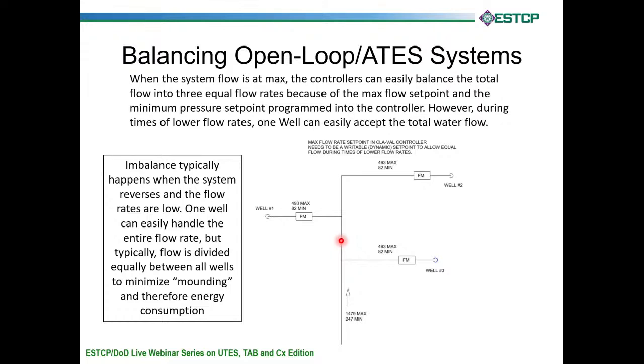One way that we have that we're working through right now to try to eliminate this problem is to get a writable set point for max flow in the injection valve controller. We're going to try that on Pensacola, and if that maximum flow set point was able to be written to constantly by the BAS system, and say, okay, we know our system flow rate is 247. We want to give this a max flow set point of 82. Now all of a sudden, it can't go over 82 without that valve starting to throttle back. Once that valve throttles back, it sends more water over here, and that should balance the system back out.